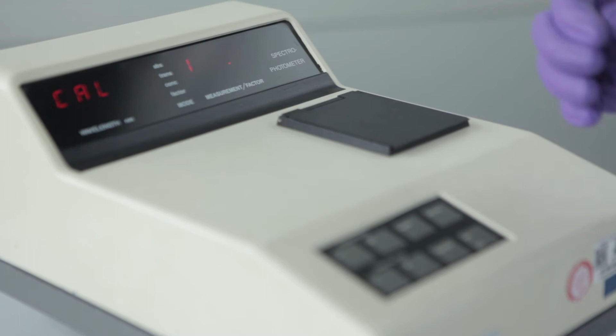We need to wait at least 20 minutes, since the lamp needs to warm up first. We've waited 20 minutes now, and the spectrophotometer is ready with the internal calibration and heating the lamp, so we can start measuring.